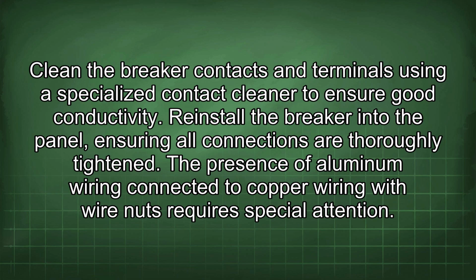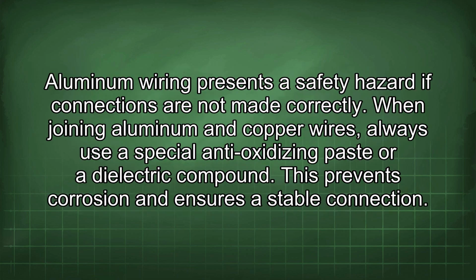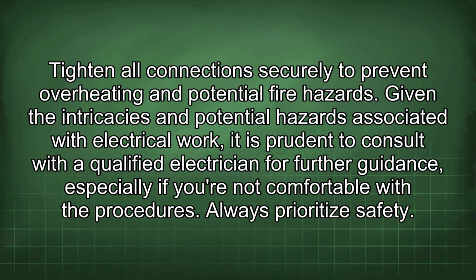The presence of aluminum wiring connected to copper wiring with wire nuts requires special attention. Aluminum wiring presents a safety hazard if connections are not made correctly. When joining aluminum and copper wires, always use a special anti-oxidizing paste or a dielectric compound. This prevents corrosion and ensures a stable connection. Tighten all connections securely to prevent overheating and potential fire hazards.